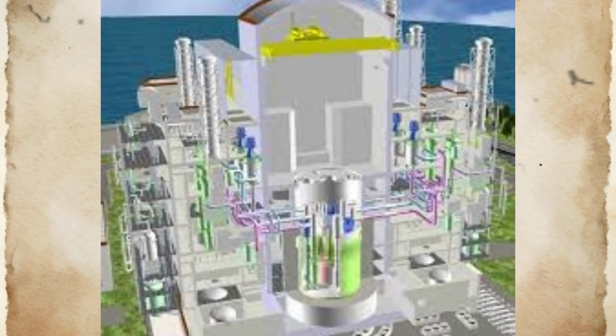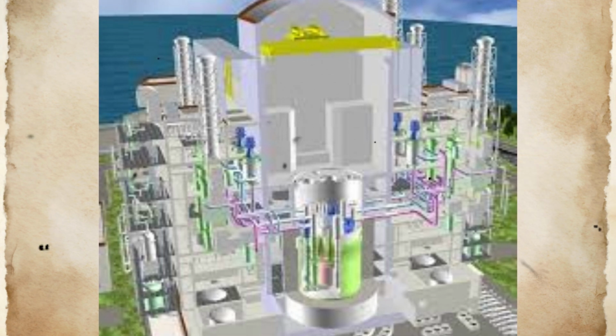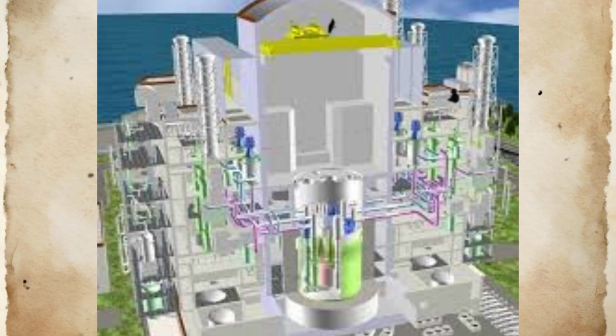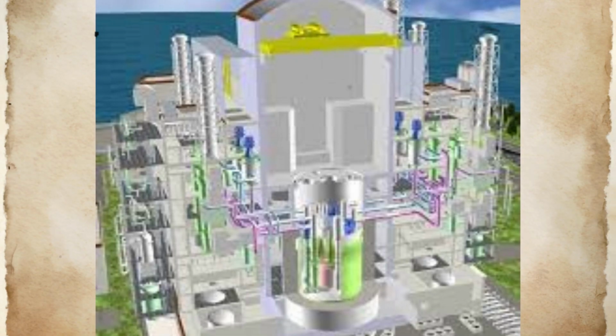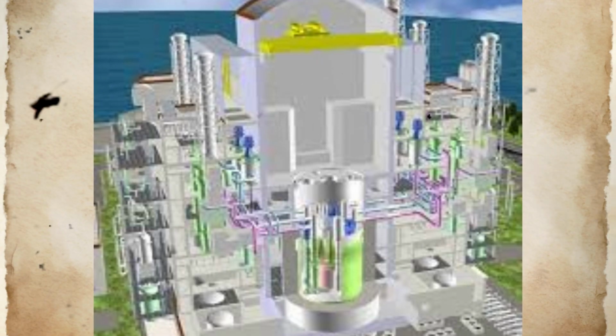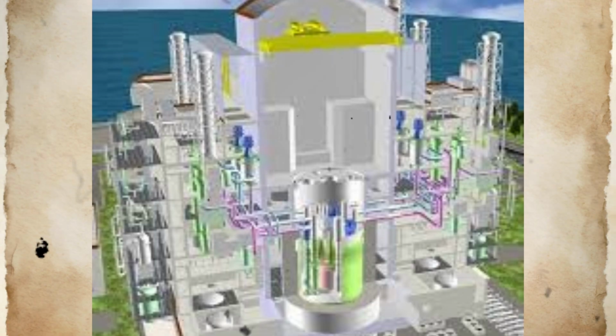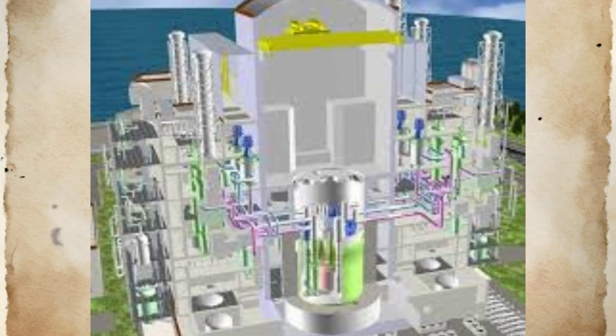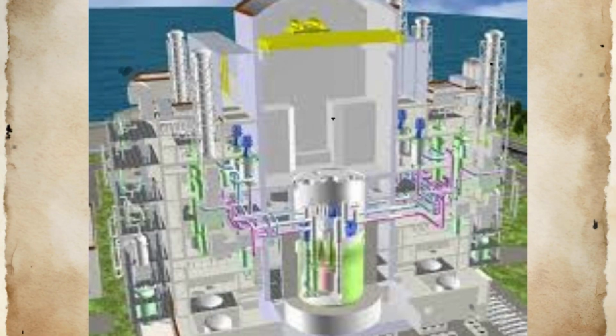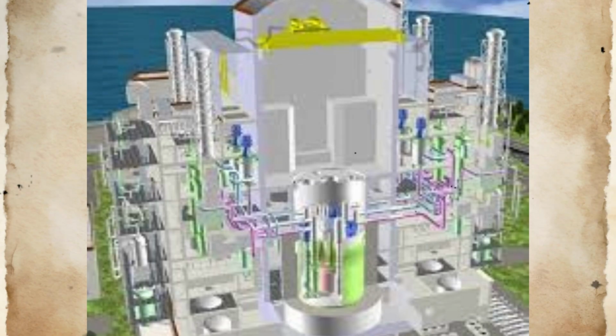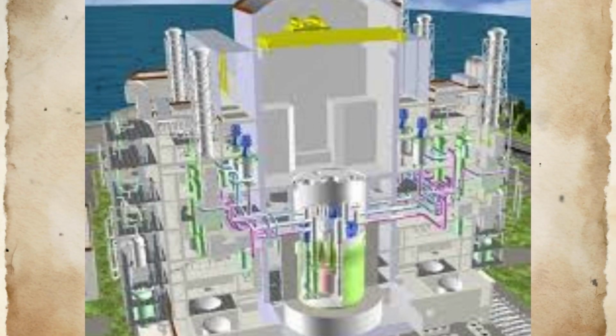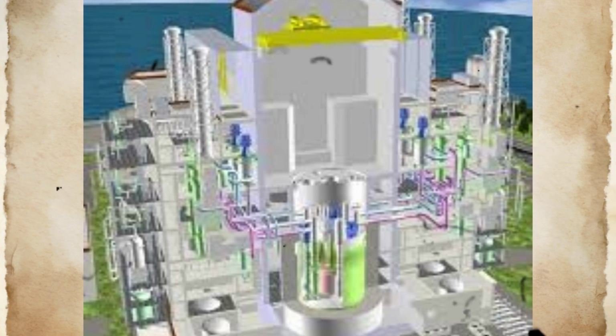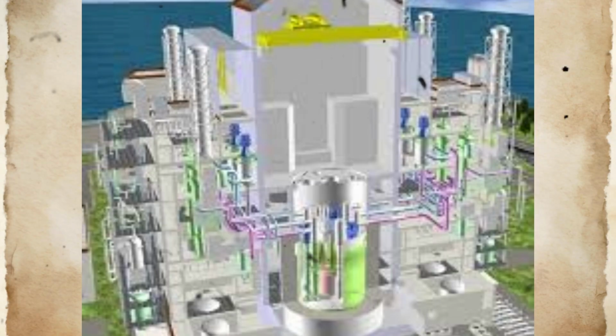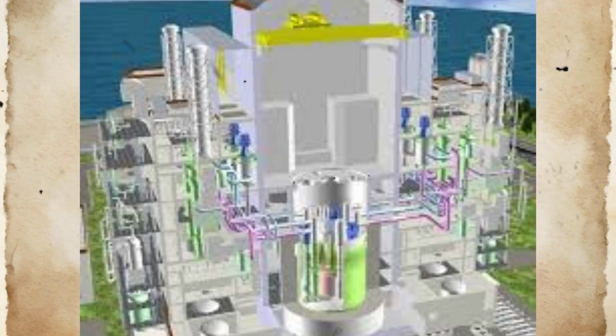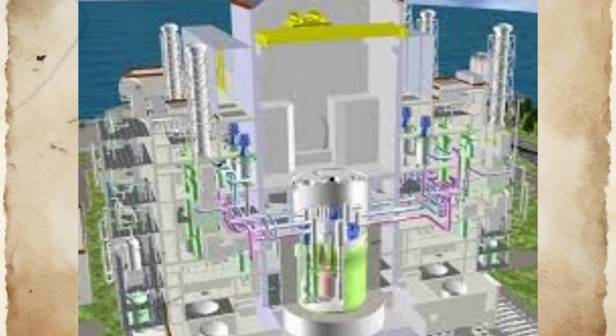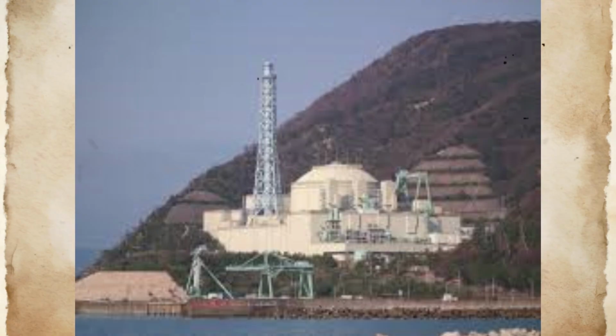The fracture of the thermocouple well tip created a direct communication path between the pressurized secondary heat transport system and the atmospheric environment of the piping room. At the moment of final separation, sodium at approximately 505 degrees Celsius and elevated pressure began flowing through the newly created opening, at a rate determined by the pressure differential and the effective flow area of the fracture geometry. The mass flow rate of escaped sodium was governed by fundamental fluid mechanics principles applied to the specific conditions present in SHTS Loop C. Secondary system pressure at the IHX outlet location was approximately 0.1 MPa above atmospheric pressure, providing the driving force for sodium ejection through the fractured well opening.